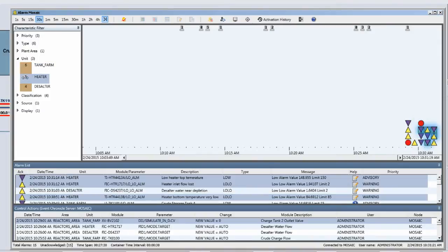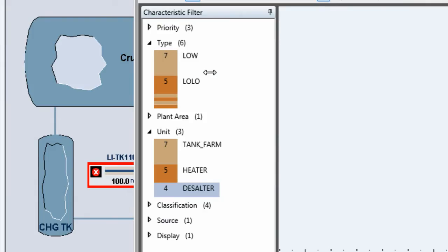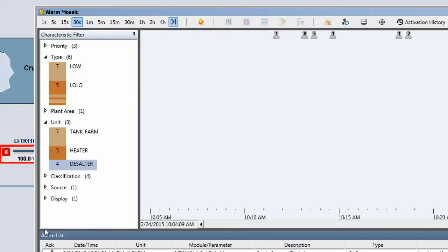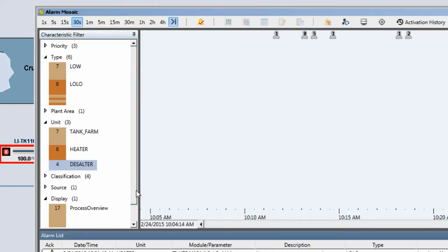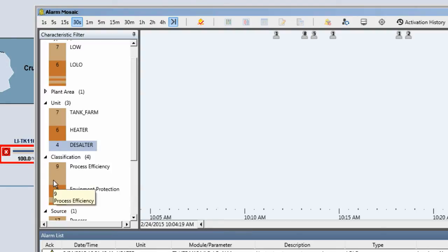You'll notice that the first three alarms that occurred were in the tank farm — quite likely where this problem originated — and then it propagated through the other parts of the plant. Other things that might help the operator gain a better overall sense of the alarm flood is by looking at type. The majority of these alarms were of the low and low-low type, an indication that something was lost — a de-energization, a loss of pressure, a loss of flow. It's also possible to look at alarms according to process displays, their source, and their classification.